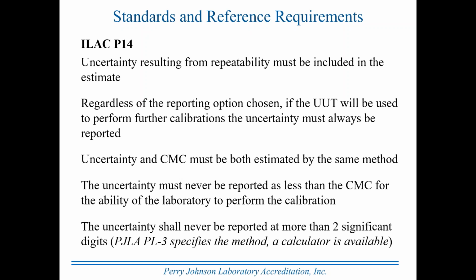The uncertainty shall never be reported at more than 2 significant digits. Now, in PJLA PL3, this is a requirement, and a method is specified for rounding numbers properly to 2 significant digits. And a calculator is available to do this from the Perry Johnson website. It's a custom Excel spreadsheet application. It happens to be one that I developed when I was the program manager, but it's available on the website for free download, and it has the Perry Johnson specified decision rule as to how to round. That's built into the calculator. So if you use it, you will always get the acceptable result for Perry Johnson.